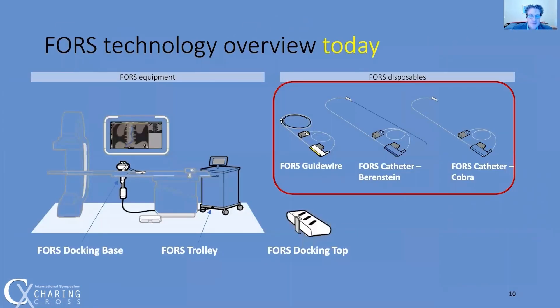The current system has the FORS guide wire and the FORS catheter, which is either a Berenstein or Cobra II in 80-centimeter lengths. The wire and catheter are connected to the base, which is attached to the table. A simple registration procedure shows the system where the wire is in space relative to the table via the docking base.